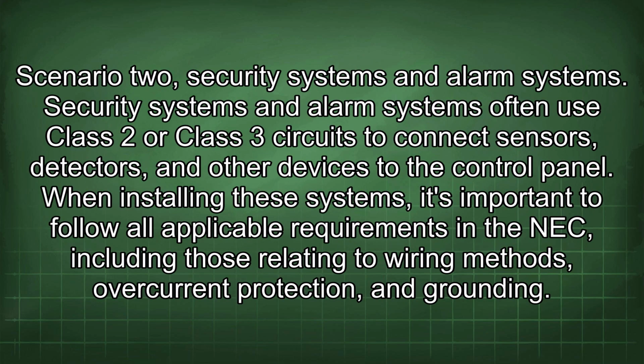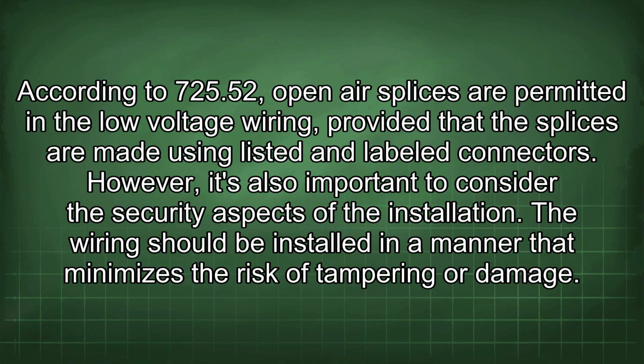Scenario 2: Security systems and alarm systems. Security systems and alarm systems often use Class 2 or Class 3 circuits to connect sensors, detectors, and other devices to the control panel. When installing these systems, it's important to follow all applicable requirements in the NEC, including those relating to wiring methods, overcurrent protection, and grounding. According to 725.52, open-air splices are permitted in the low-voltage wiring, provided that the splices are made using listed and labeled connectors.